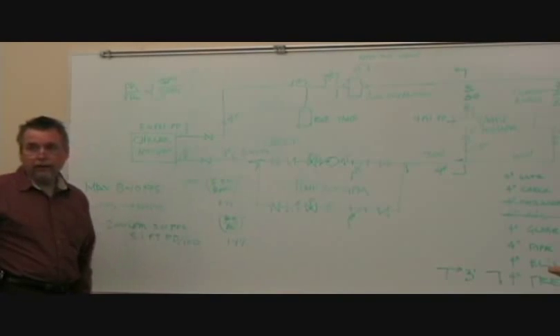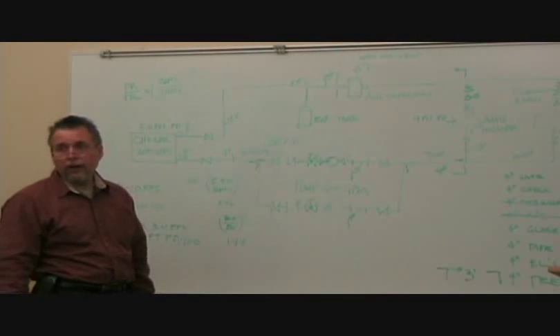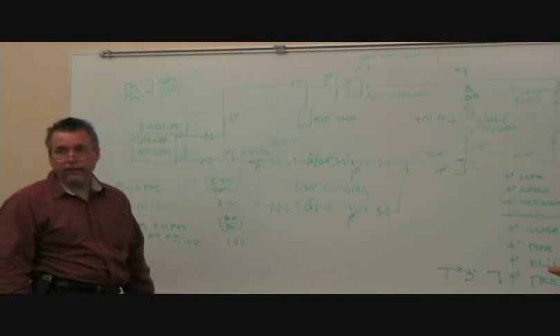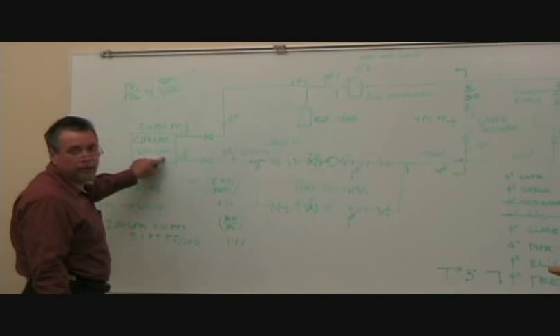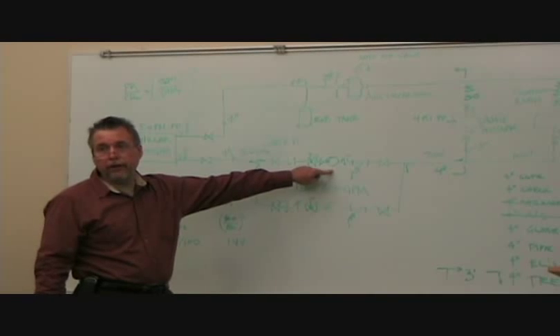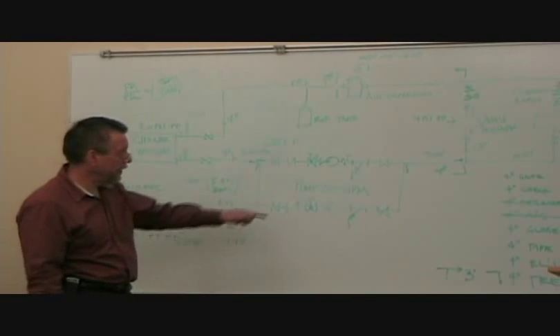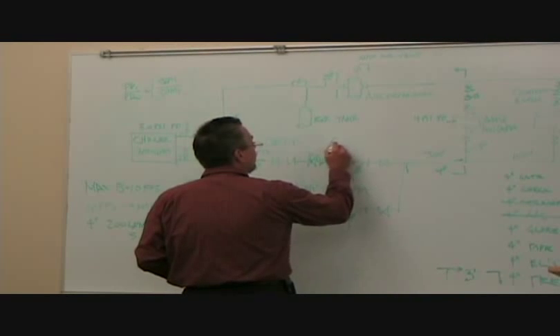So again, all I need to know is what the original conditions were and then measure the pressure drop, and I can calculate what your flow should be. But I don't know how much pipe, I don't know all the fittings, so I can't predict the system loss without actually going in and calculating. I can know what the system loss is, because if I can measure the flow here, I can measure the head here and compare it to what was originally designed. For instance, we're designing our pump at 60 feet of head, 60 feet at 200 gallons per minute.